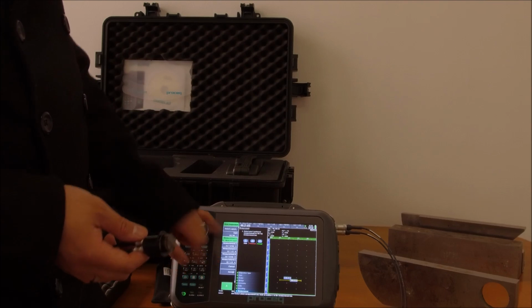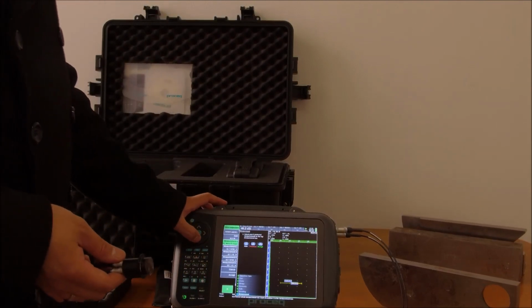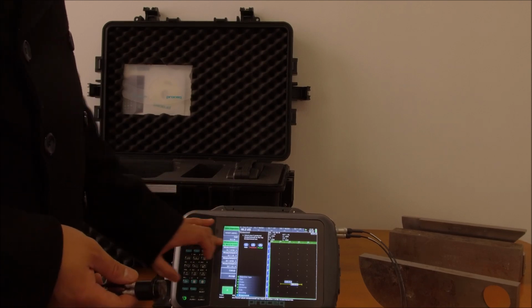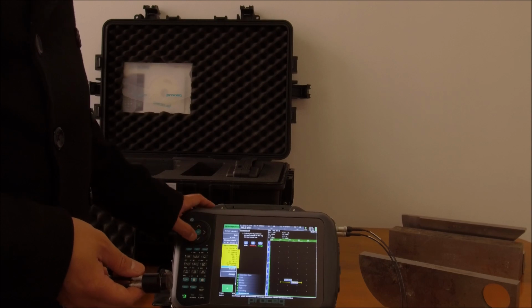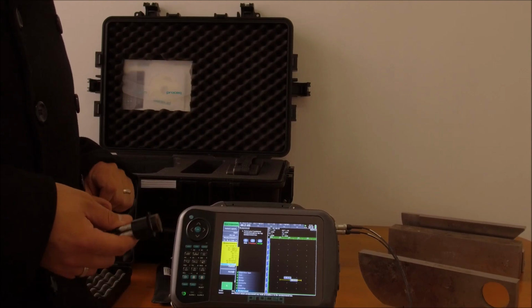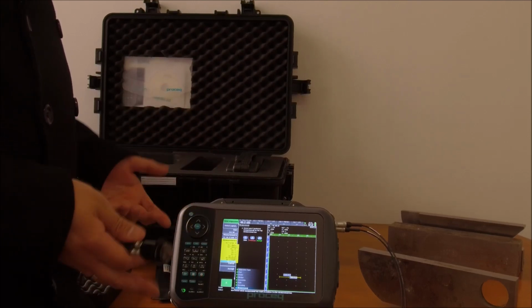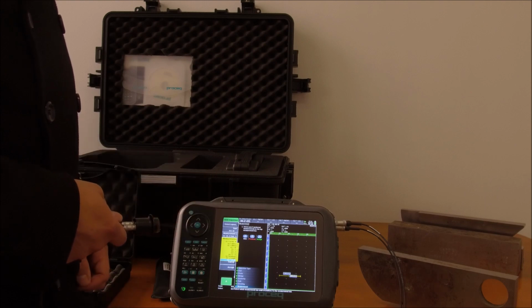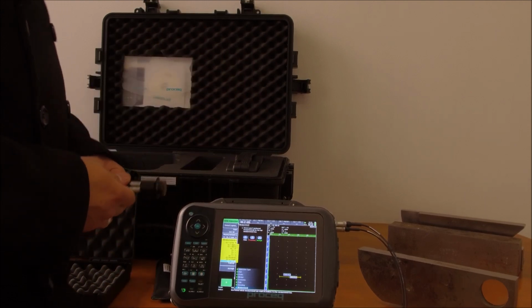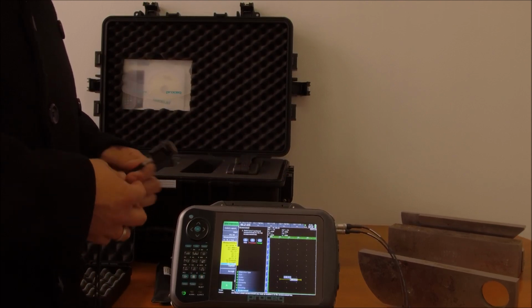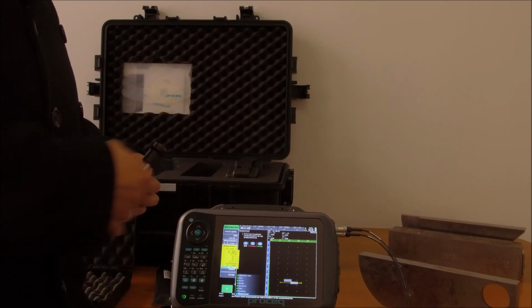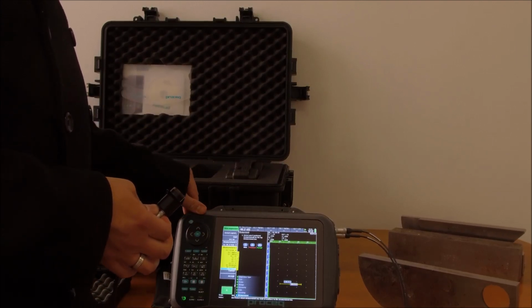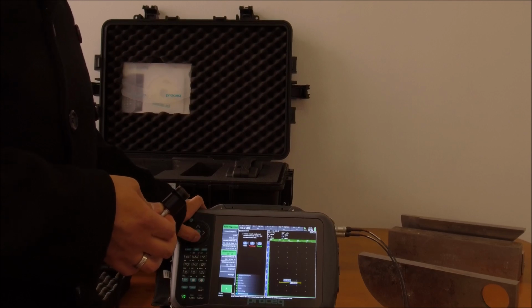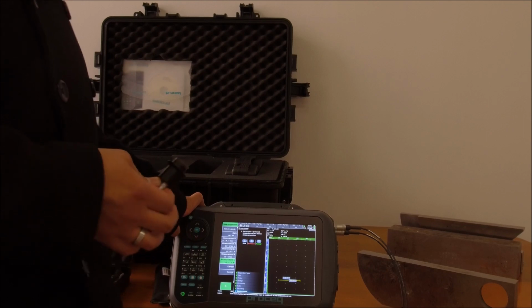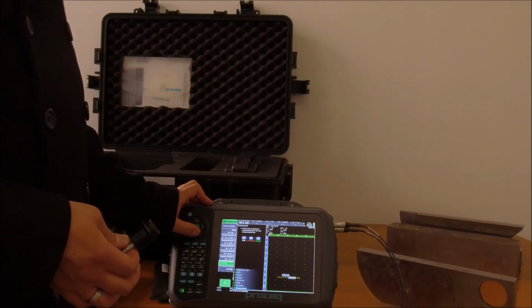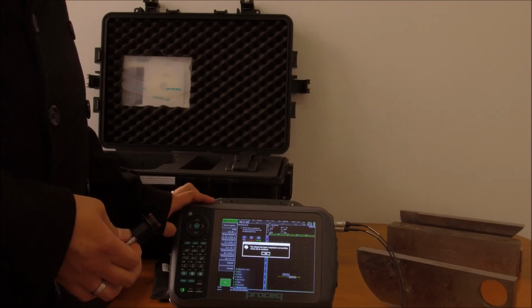These options here represent these options up here. The first one that I've got for measurement 1 is your mono pulse echo gain. I can then change it to all sorts of things relating to AWS, relating to DACs, relating to full percentage of full screen heights. I can put in my projection distance for an angle probe, my estimated depth, my actual time base, or how long the sound has actually taken to get there. So we'll just leave it at this point, but you do have lots of options to set this up just how you want to set it up. At this point, I'm just going to accept.